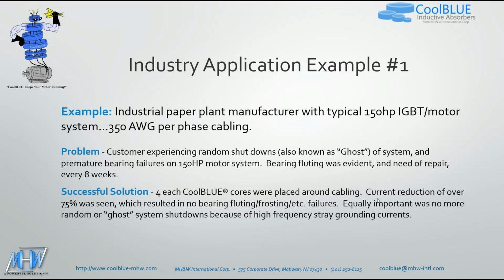Paper plant manufacturer, 150 horsepower VFD motor system. They had 350 gauge per phase of cabling. The customer was experiencing shutdowns, known as ghost shutdowns, of their system. And they also had premature bearing failures on a 150 horsepower motor system. They were getting fluting and had to basically repair the bearings every 8 weeks. We put 4 CoolBLUE cores on the cabling. Current reduction of over 75% was seen, which resulted in no bearing fluting, frosting, etc. Equally important, there were no more random or ghost system shutdowns because of high frequency stray grounding currents.